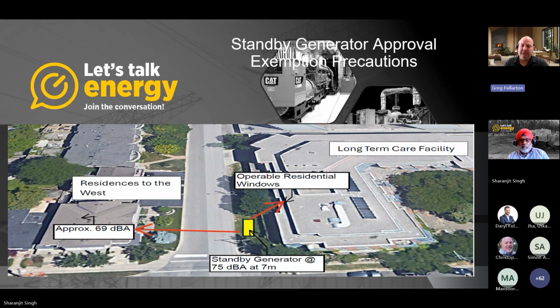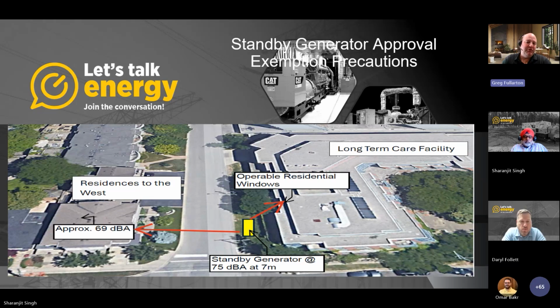I'm going to throw it wherever the shortest conduit run is, because copper's at a premium today. When you take a look at placing this generator here, we have a few problems. Let's assume this house is 14 meters away. The standby generator's at 75 decibels at 7 meters. When you measure the sound levels over at this point, it's only going to come down to about 69 decibels. So they're being impacted with 69 decibels every time that generator is put on test.